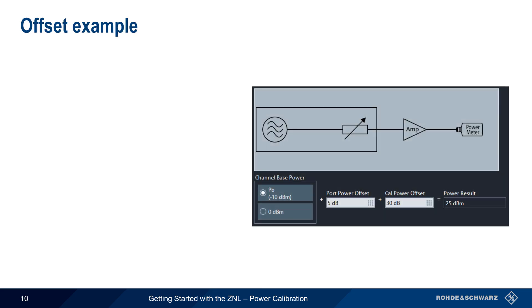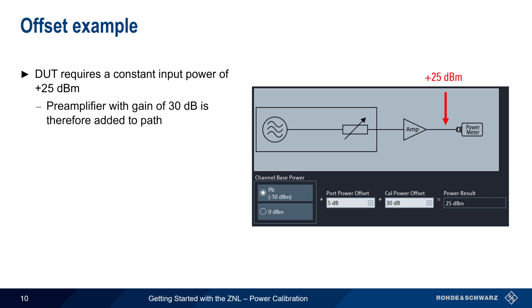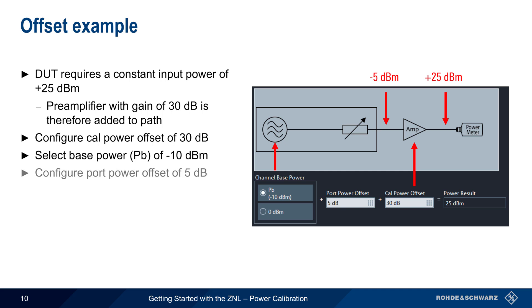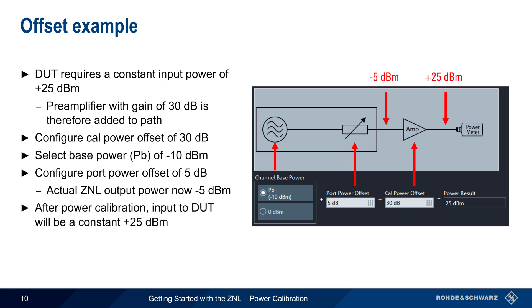Let's walk through an example using offsets. Here, our device under test requires a constant input power of plus 25 dBm. In order to reach this level, a preamplifier with a gain of 30 dB is placed between the ZNL and the device. We start by configuring a CalPower Offset of 30 dB to match the gain provided by the preamp. In order to obtain plus 25 dBm at the DUT, the input to the preamp — that is, the output power of the ZNL — must be minus 5 dBm. We therefore set the ZNL base power to minus 10 dBm and set the Port Power Offset to 5 dB, so that the actual ZNL output power is minus 5 dBm. Once power calibration is completed, the input to the device under test will be minus 5 plus 30, or plus 25 dBm.